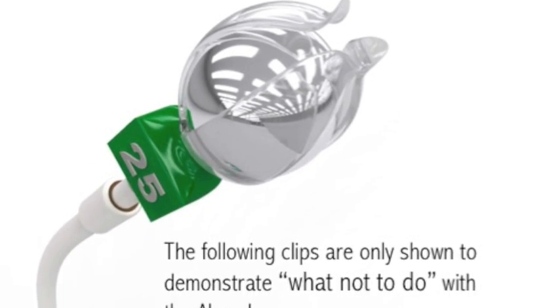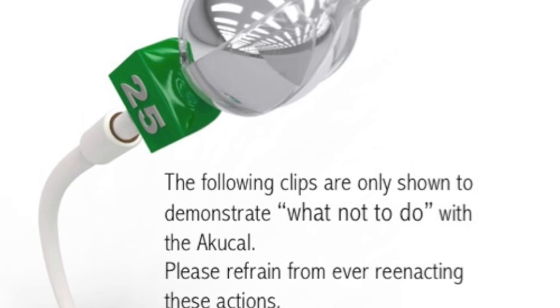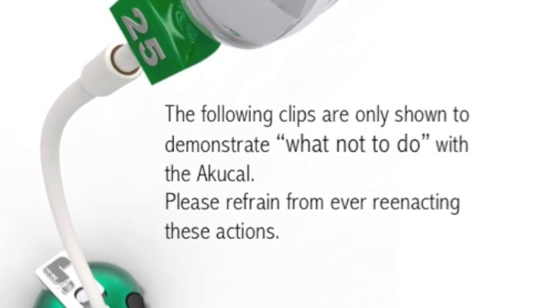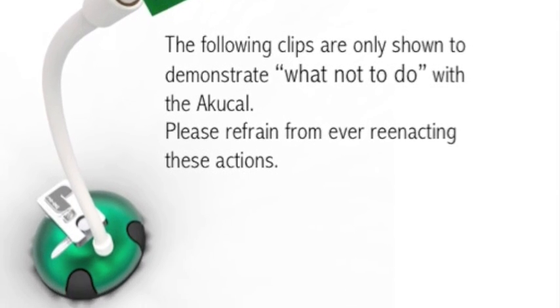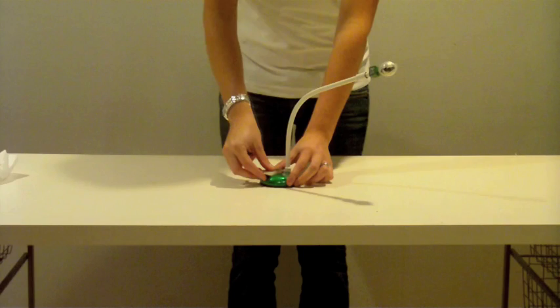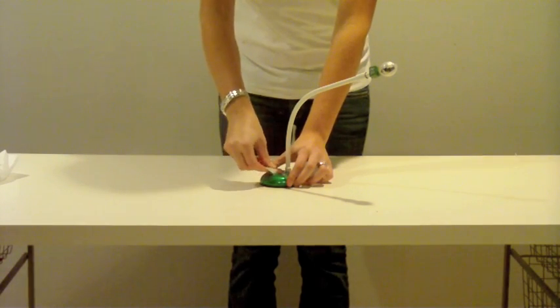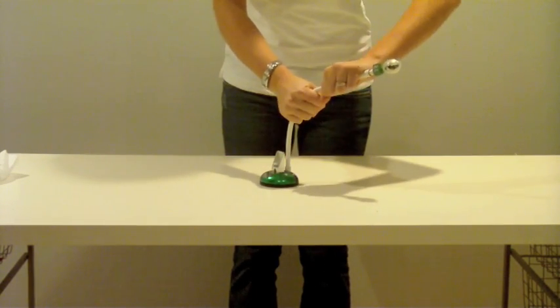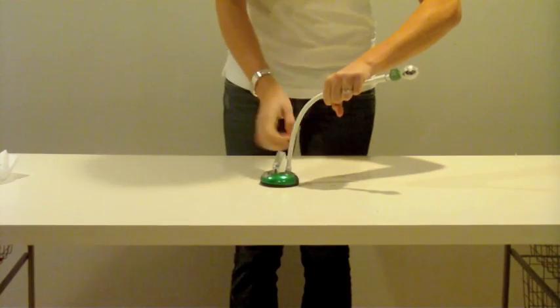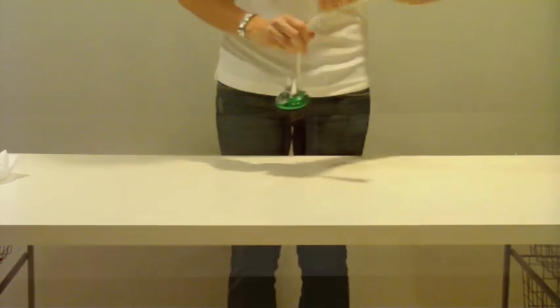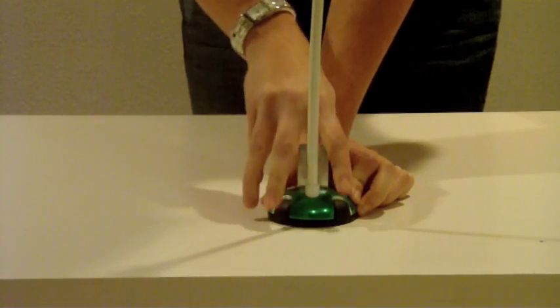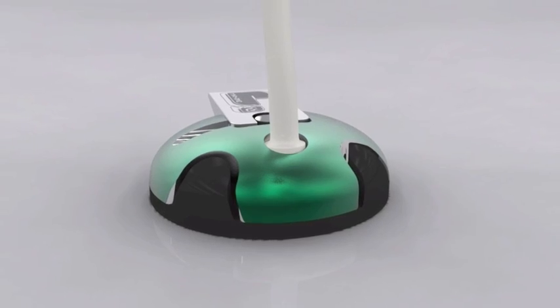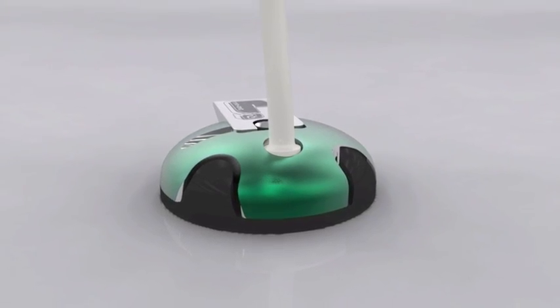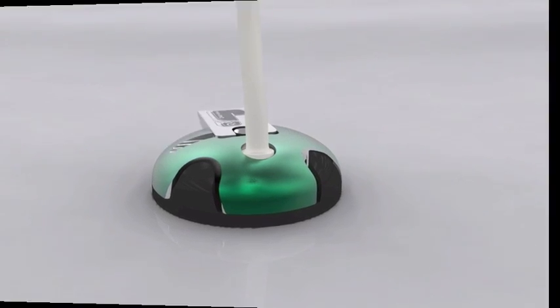The following clips are only shown to demonstrate what not to do with the Akucal. Please refrain from ever reenacting these actions. The arm of the Akucal should never be used to assist in removal. Repetitively and forcefully removing the Akucal by the arm can damage the arm and/or base. If the suction cup does not immediately remove from the table or upright bucky after the lever is released, remember to depress each rubber tab to break the seal.